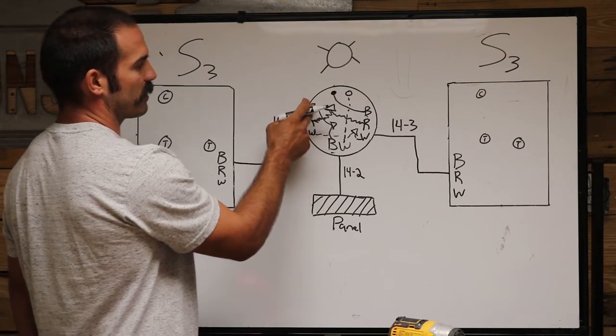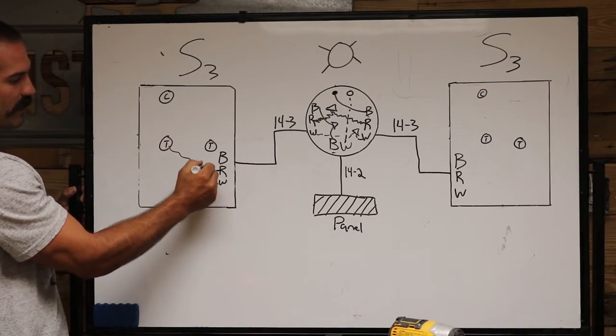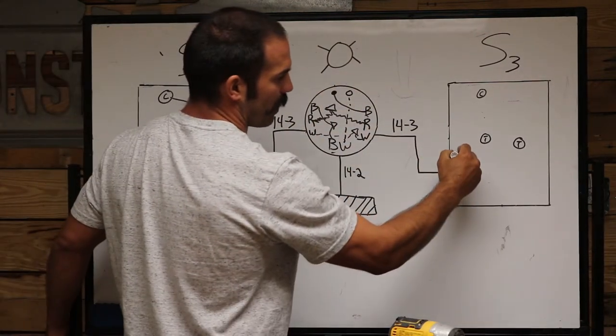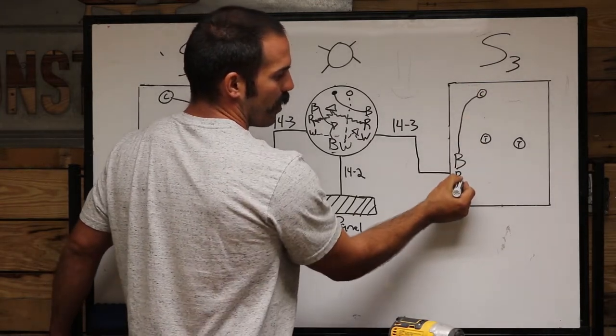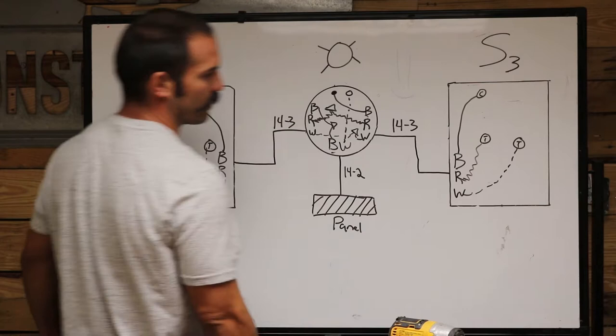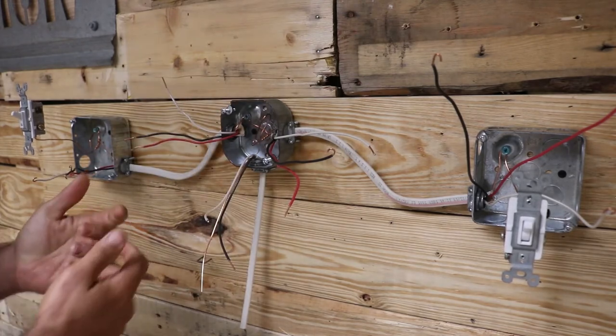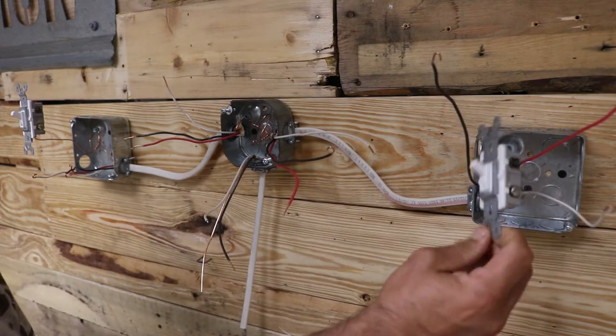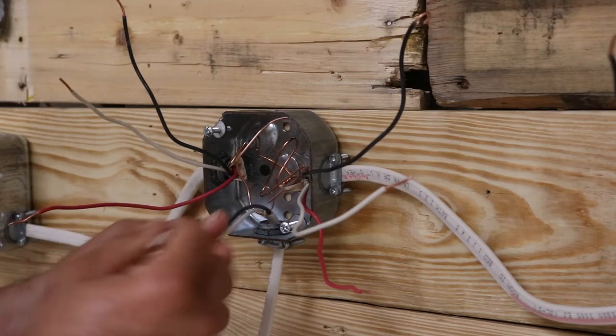This hot wire will attach to the hot wire which takes us over here — our red is a traveler screw, our white is a traveler screw. This hot wire right here will go to the black common screw on the three-way. In the other box, the black wire is the switch leg — it'll feed that common screw. We attach the red wire to a traveler screw and the white wire to another traveler screw. Power comes into our light box and between the three-way switches we always have 14-3 running, with three-way switches on each end.